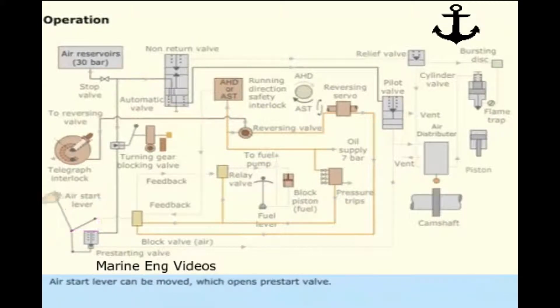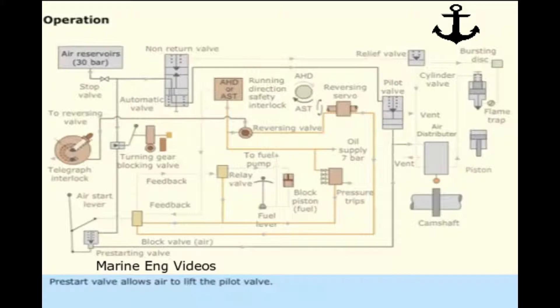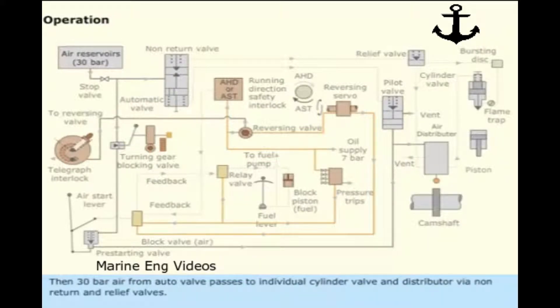The air start lever can be moved, which opens the pre-start valve. The pre-start valve allows air to lift the pilot valve. This causes the bottom of the pilot valve to vent the opening air. Then, 30 bar air from the auto valve passes to the individual cylinder valve and distributor via non-return and relief valves.